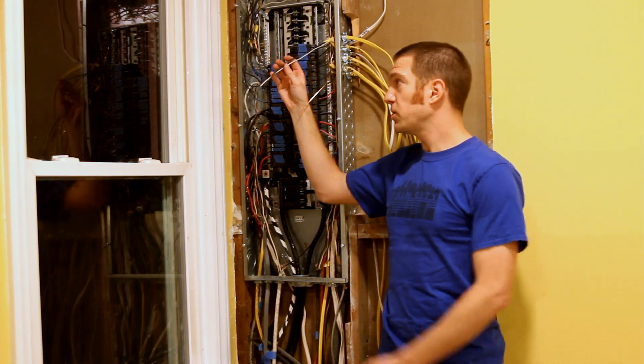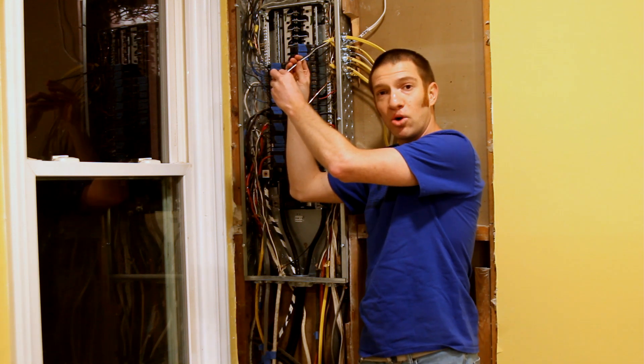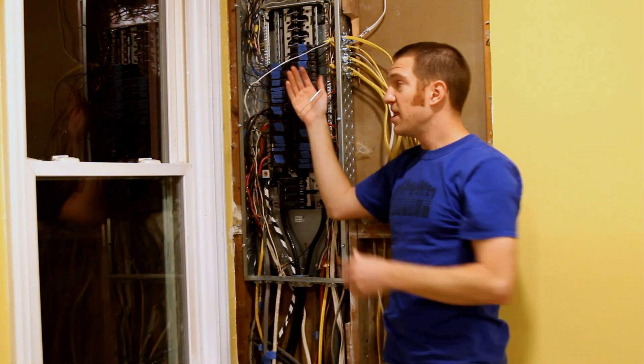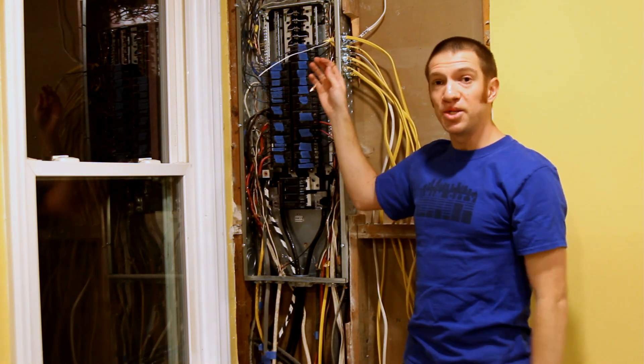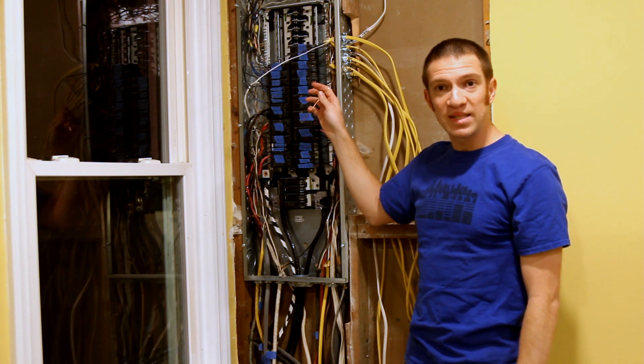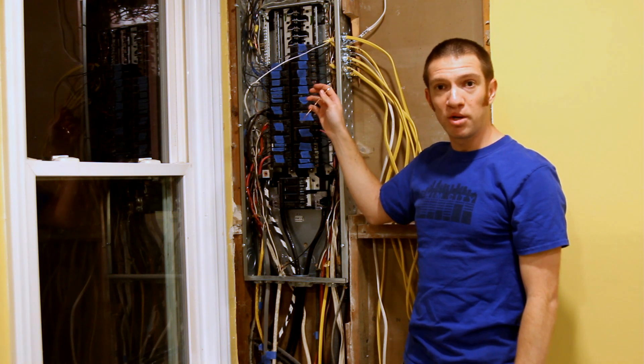And I don't need it yet, so I'm not going to install a breaker. What I'm going to do is I'm just going to go ahead and put a cap on the neutral hot wire, and then this ground wire does need to be grounded, so I'm going to go ahead and fasten that to the ground bar.